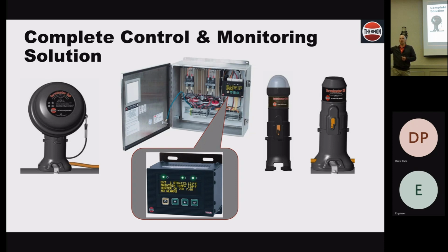Not to get too geeky, but it's a one-to-one versus a one-to-many relationship. With ambient, you have a sensor out there floating wherever it is, and if it gets cold, all your heat trace turns on. With line sensing, you might have a couple different lines, MI cable lines, process lines, that you're maintaining at 150 or 170 degrees. You need sensors on those pipes uniquely, individually, so you know those pipes are at 170, and these other pipes over here are all freeze protection. Those are conversations we love to have because we can help optimize that design from a whole plant standpoint. Those are the really fun ones.